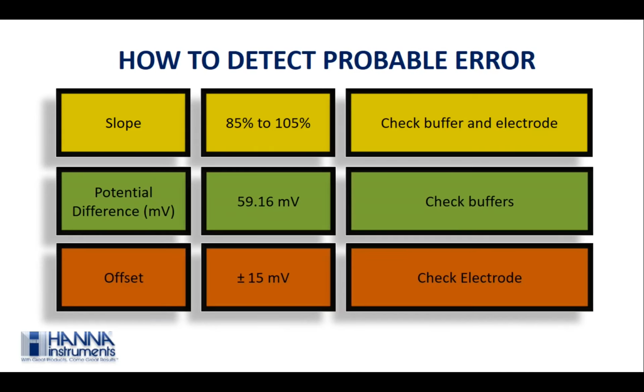So how to detect potential error? Whether the error is in the meter, in the electrode or in the buffer. The key to determine error due to calibration is the millivolt of each calibration point. Each and every known standard buffer generates a particular millivolt. Any change in these millivolts will make you understand the potential error. If the millivolt generated in the offset has a large difference, beyond the acceptance window, and is carried on to the slope values as well, then there is a deposition on the electrode. If the difference in the pH unit is high, then check your buffers and more.